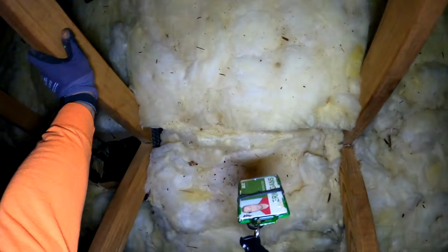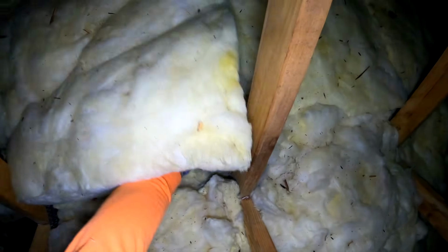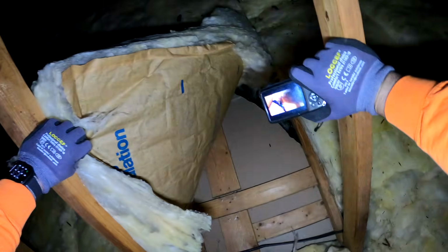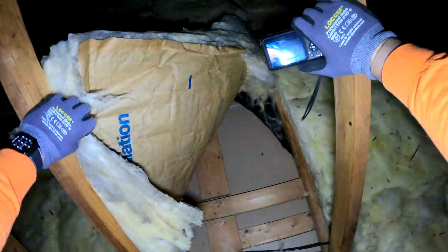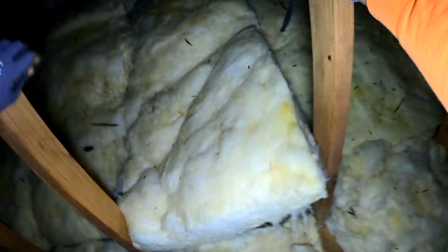The next thing that I see all the time is insulation that looks like it's in place and it's flat, and you can see from the hatch that it's there. But when you inspect it a little bit more closely, you see that it is not in contact with the surface that it's intended to insulate. And if it's not in contact, it is absolutely unable to do its job.